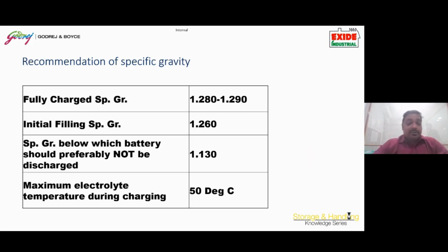Now, the specific gravity below which a battery should preferably not be discharged is 1.130. So you have been running the forklift the whole day, and at the end of the day the forklift gives a message that the battery has lost its capacity, and if you measure the specific gravity and it is somewhere around 1.130, that is an alarm. You must put the batteries back on charge again. 1.130 specific gravity means that we nearly have no electrolyte left in the battery, only water, and the active positive and negative plates have lead sulfate and no more spongy lead. So this is the condition wherein we must immediately put the batteries on charge.